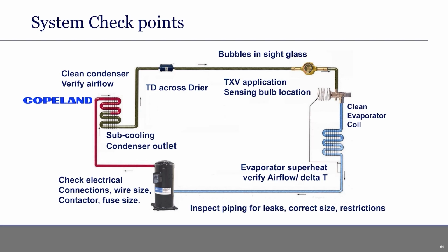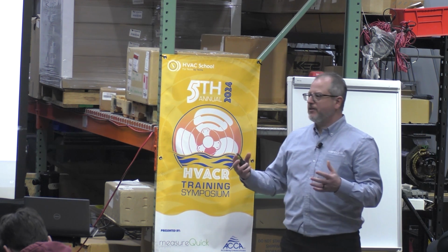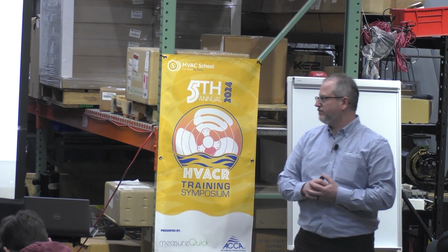All right, so there's so many different things that we can check in our system. If we have a 2 to 3 degree temperature difference in our filter dryer, we probably have a problem, right? We want to make sure we have subcooled liquid going to our metering device, right? We can check our temperatures, our pressures, our superheat. We can check our amps, our compressor superheat, our discharge, our compression ratio. We can make sure that our condenser's clean, we have good subcooling. So many different things to check on our system before we start adjusting things.